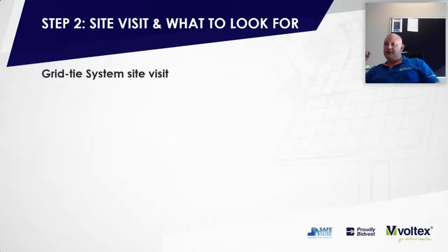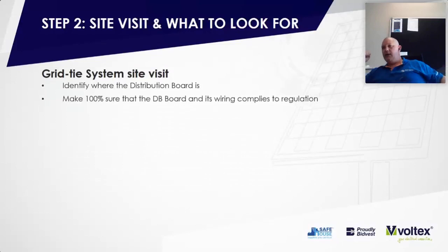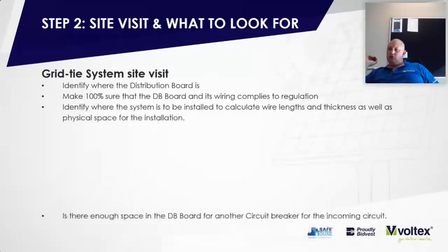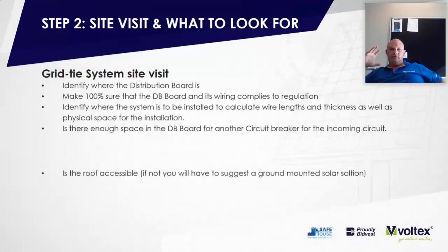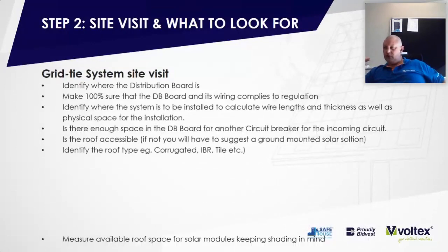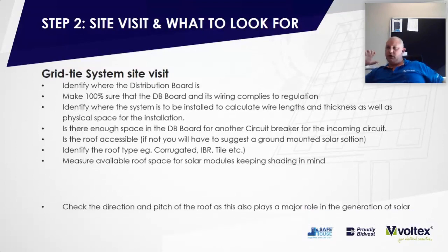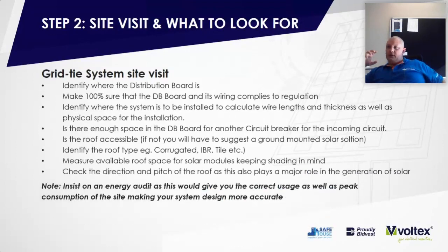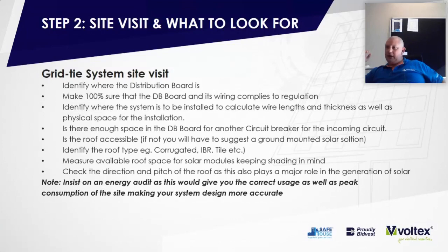Grid tie system site visit, pretty much similar to the rest, only that you do not need a lot of space because there's no batteries involved. The system is purely inverter and distribution board. On this system, similar to the others, compliancy, where the DB board is, where the system is to be installed. In this case, you need to look in the DB board and see if there's enough space for another circuit breaker to have access to that specific circuit powering your house from alternative energy.